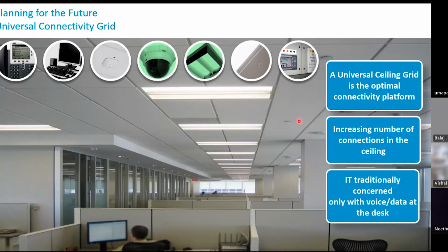We have something called a universal connectivity grid. What you can do is have a larger number of points on the ceiling itself. Whenever you work on a connectivity requirement for a floor, you don't need to depend on a heat map to work on the access point, then the CCTV point, then the light systems, everything. What the standard says is you convert that ceiling into multiple grids and provide the number of points required on each and every grid.